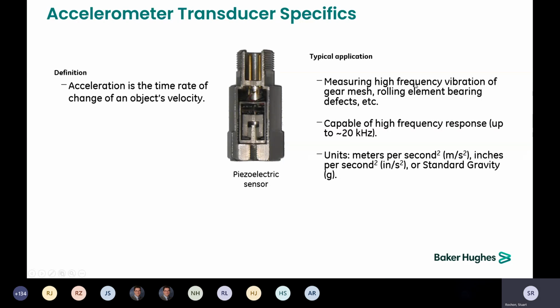Accelerometers are better for measuring higher frequencies, quite often used around rolling element bearings and internal gear mesh measurements, and can go up to 20,000 hertz. As you get higher in frequency, the reference mass has to go down due to the inertia of the reference mass. Getting a 20-pound weight to change direction 20,000 times a second is nearly impossible. The amount of energy required is monstrous, but getting a gram or less of mass to change direction 20,000 times a second takes much less energy.